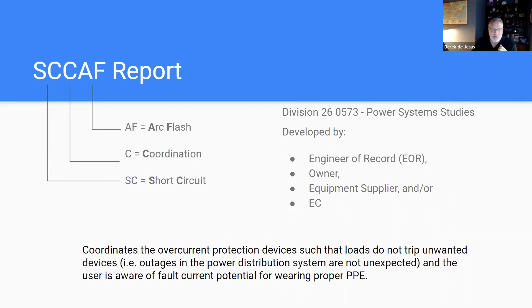And that is right here. I'm just going to draw on my screen so everybody can see it. So that is usually provided right here, but there's other things that you can validate as well. The CT ratios, you can validate; if this was a breaker, you'd see frame sizing, you'd also see the plug rating as well. So there are other things that you could validate on the table just to make sure that the study has a good fundamental baseline.